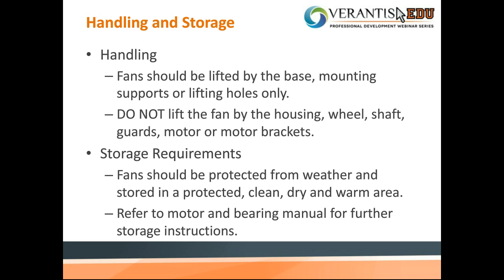Storage requirements: if you're not going to be using your fan for a lengthy period of time, the fan should be protected from weather and stored in a protected, clean, dry, and warm area. Always refer to the motor and bearing guidelines within the manual for further storage requirements. Most fans will have not only the fan operating information, but also information on the standalone components like the bearings and the motor. Sometimes there's some information on the belts in there. Just feel free to review it. There's always some really good information in there.